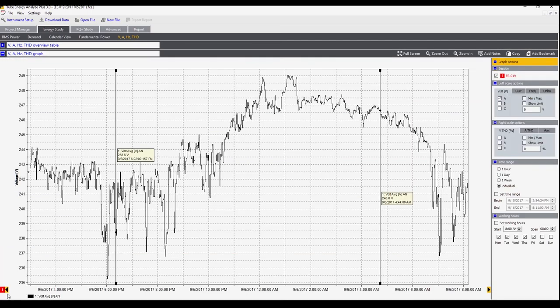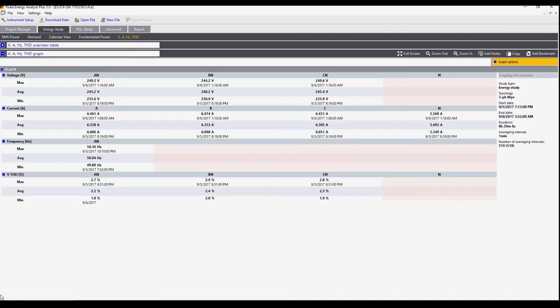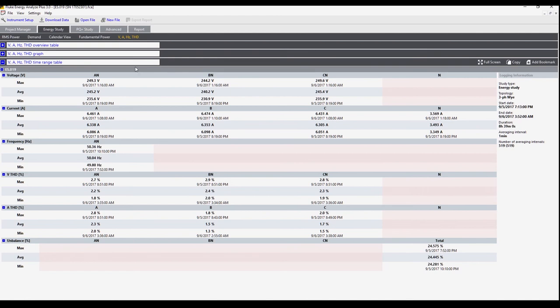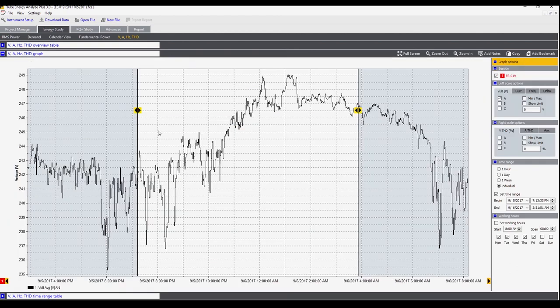Let's open the graph again. We can select a range that we're interested in here. We go to the set time range and now we can see just a portion of the graph, and that gives us a second overview section here. This again shows the minimum, maximum, and average values for each of the phases and each of the measured values. This data, rather than applying to the whole measurement, only applies to the values shown between these two cursors.